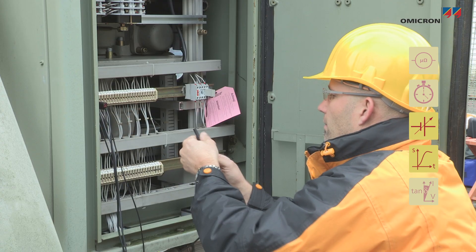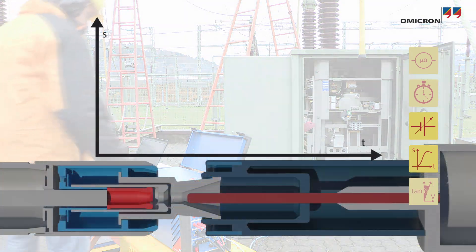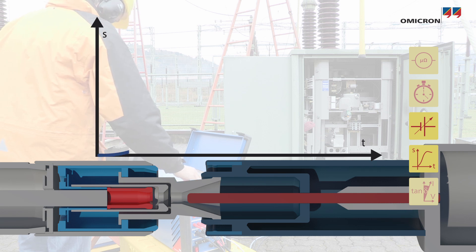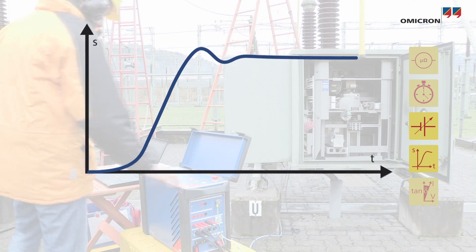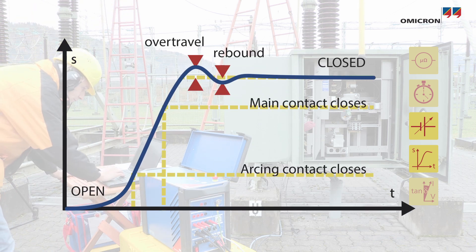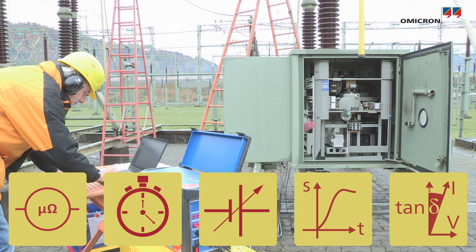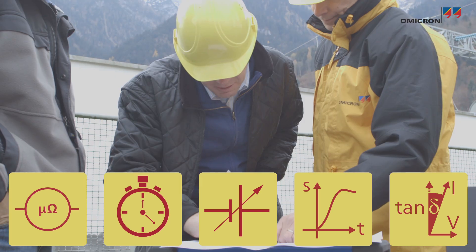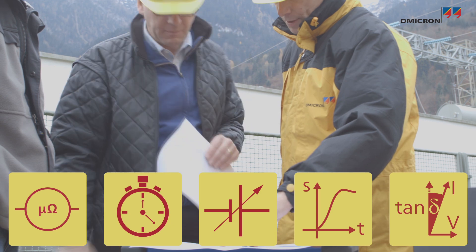Additionally, if the circuit breaker travel curve is recorded, it allows mechanical parameters to be assessed such as velocity, total travel, acceleration, over-travel, and rebound. By performing these measurements, the station operator can verify that the equipment is in good working condition or can initiate maintenance activities.